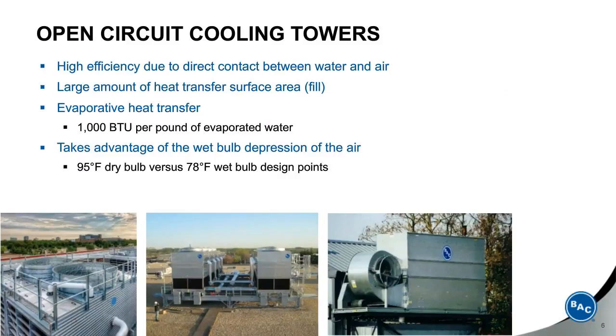Now, open circuit cooling towers are highly efficient, and that is due to the direct contact between the water and air on the fill surface. There's also a large amount of heat transfer surface area in these units, which enhances the efficiency. The heat transfer is also based on evaporative heat transfer, because to evaporate 1 pound of water requires 1,000 BTUs, so it takes away a lot of heat with just a small amount of water. So you lose about 2% of the water to evaporation, but that evaporation then cools the remainder of the water very efficiently close to the wet bulb of the air.